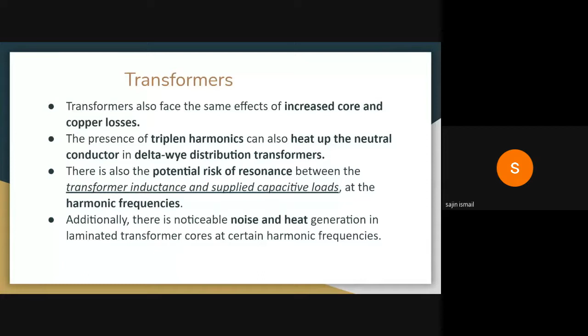Now we can come to the transformers. Transformers are a potentially high risk component in a grid, where the distribution transformers deal directly with the EV chargers. So what happens is, if these harmonics are not taken care of at the charger level itself, and if they are injected into the grid, it will definitely hamper it, because we know the distribution transformer primary is delta and the secondary is star connected. So the primary may not be affected by these harmonics because of the delta connection, but the secondary windings may be affected. There is also a potential risk of resonance between transformer inductance and the supplied capacitive loads. This is only a potential risk being suggested, and it arises at harmonic frequencies, only if the harmonic frequencies are predominant. As we know, noise and heat generation will also be there due to harmonics. I'm not stressing much on harmonics.